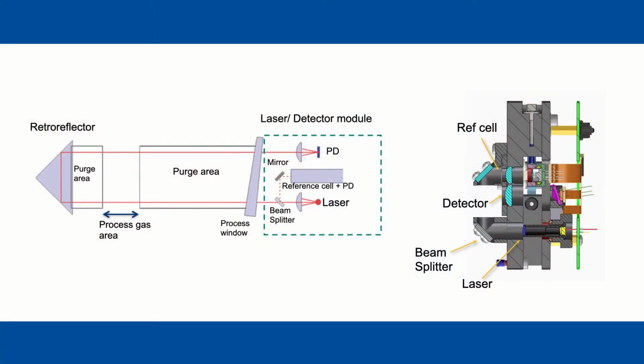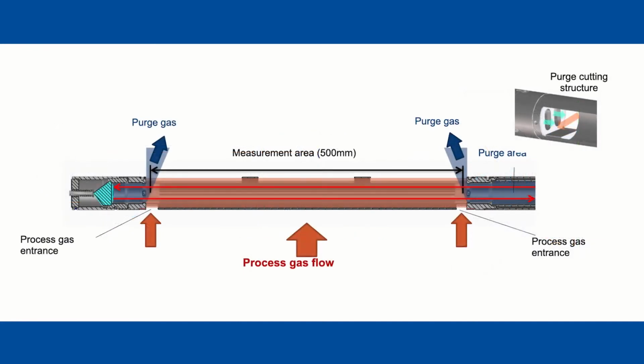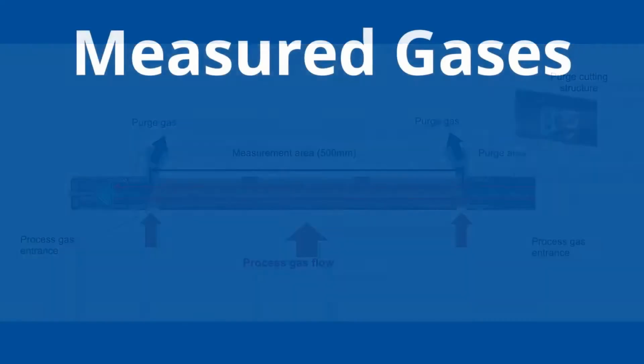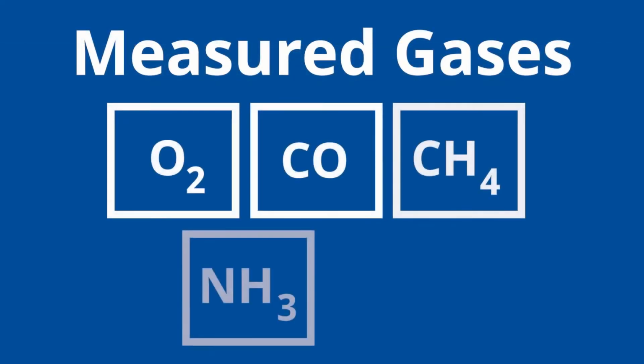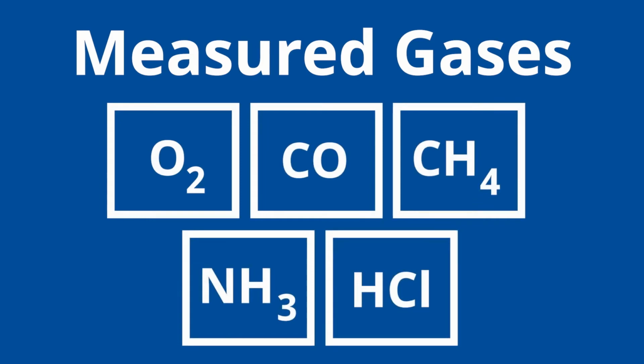Here's a more detailed view into how that works. The process windows isolating the process from the electronics are kept clean by a purge sweeping each end of the entry for the process gas measurement area. Of course, the window purge should be optimized based upon the process gas flow rate. Measured gases include O2, CO, methane, ammonia, and HCl. CO and methane can be measured by a single analyzer. Please feel free to contact us for any other desired gases, as we're always looking to expand our measurement portfolio. Currently, we focus on gases which absorb in the near-infrared wavelength region.